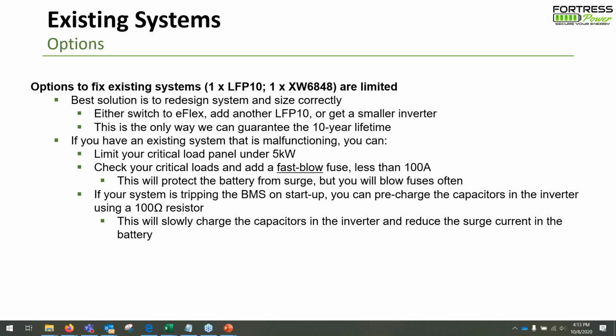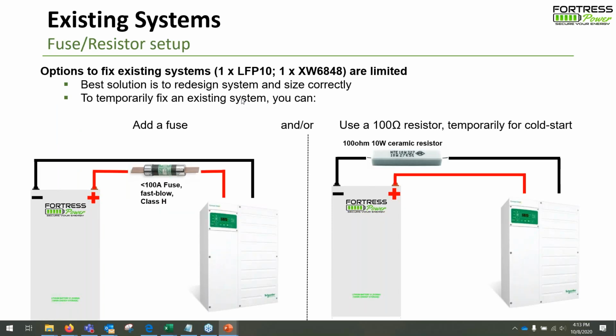Now I'll go into this right now a little bit so you can see. Okay, so existing systems, the fuse and resistor setup. These are the two things that I think we recommend for these existing systems that cannot be changed. Again, the best solution is to redesign the system and size it correctly. To temporarily fix an existing system, you can add a fuse. So a less than 100 amp fuse, maybe a 90 or 80 amp fuse, fast blow class H will work on the positive terminal between the battery and the inverter.